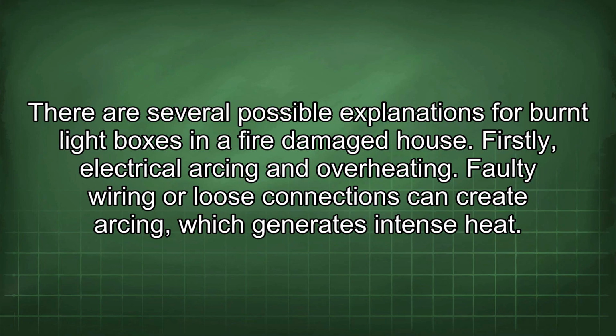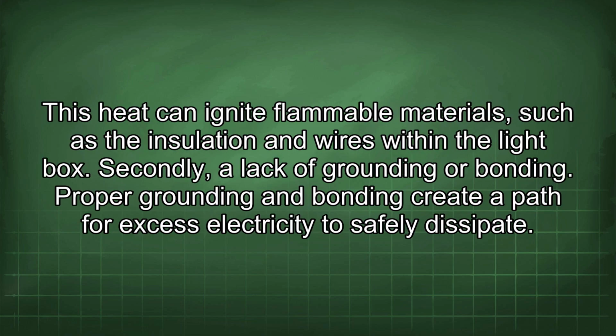There are several possible explanations for burnt light boxes in a fire-damaged house. Firstly, electrical arcing and overheating. Faulty wiring or loose connections can create arcing, which generates intense heat. This heat can ignite flammable materials such as the insulation and wires within the light box.